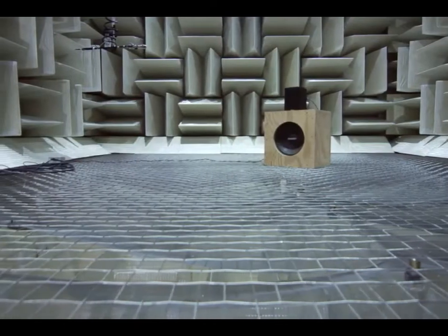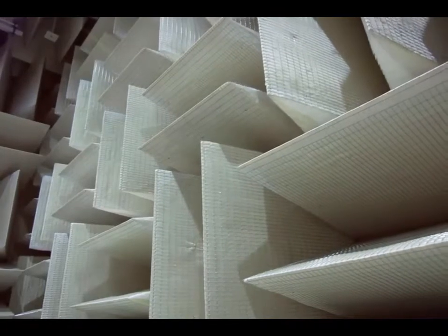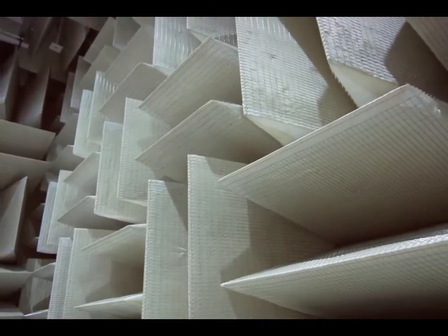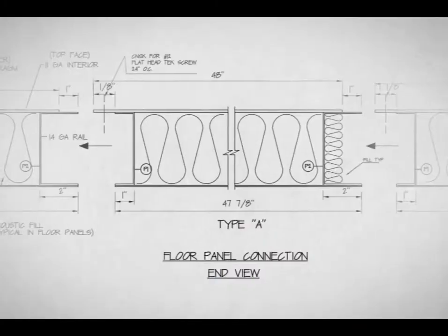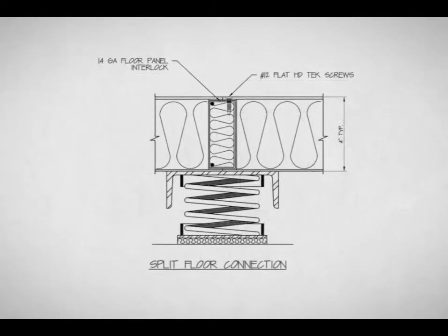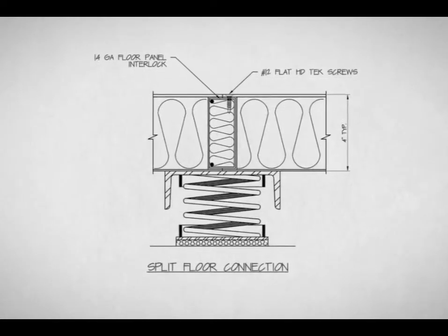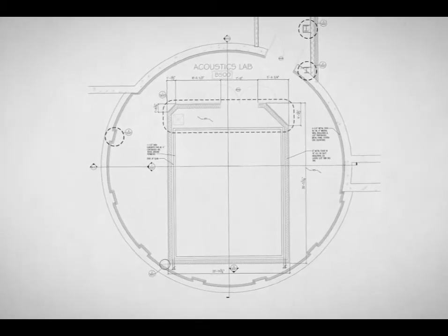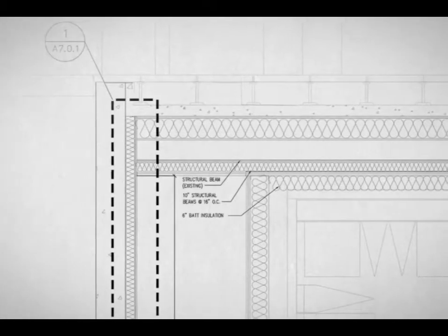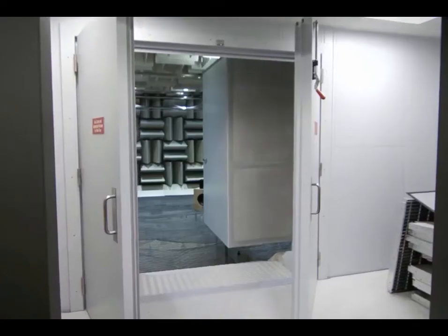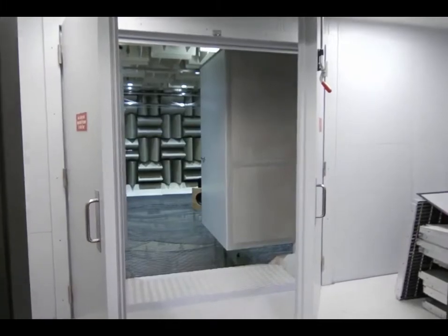The chamber is designed to just suck up all the sound, and it sits on springs, so it's not directly connected to the rest of the building, to keep it as quiet as possible. It's something that we spent a lot of time designing, and it met our specifications by far, and is really one of the quietest places you can go.